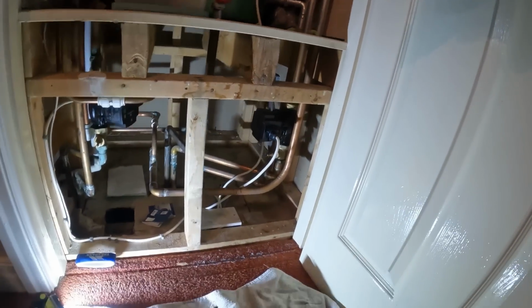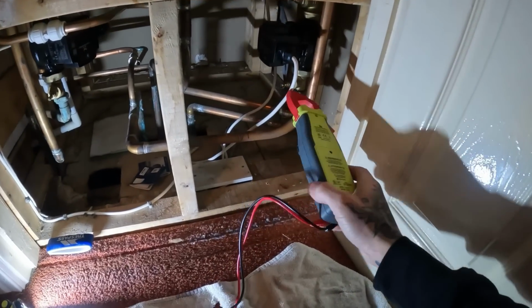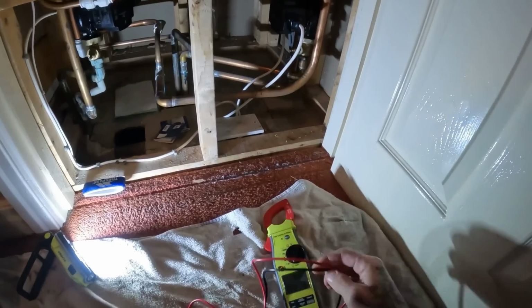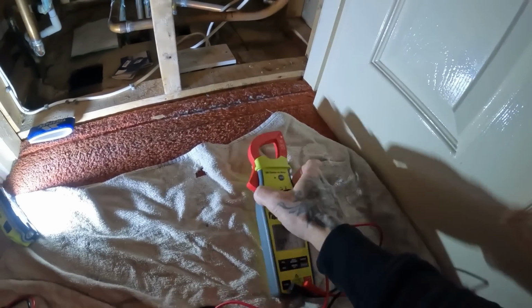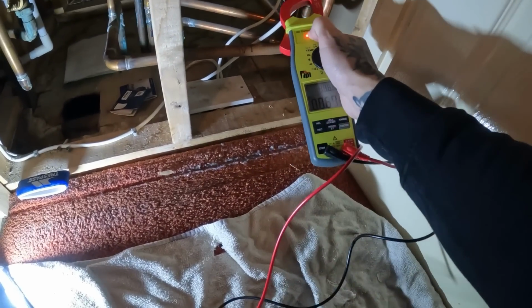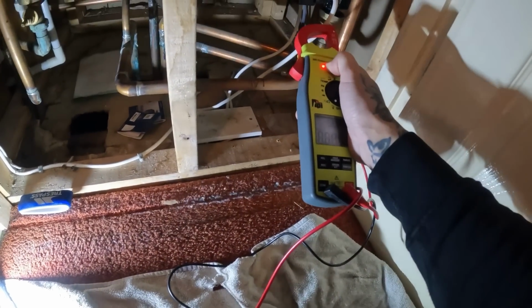That pump there is the one that isn't working. I've got an error code on it, but first I'm going to check there's definitely power, using a non-contact voltage tester, TPI, and a multimeter. As you can see, there's no power on that one, but we've got power on the central heating.